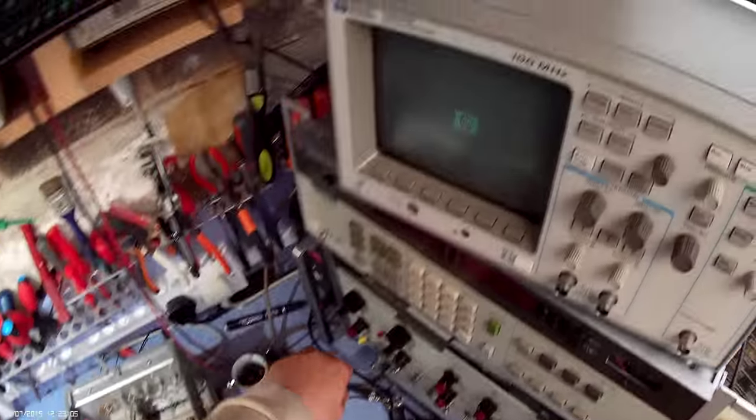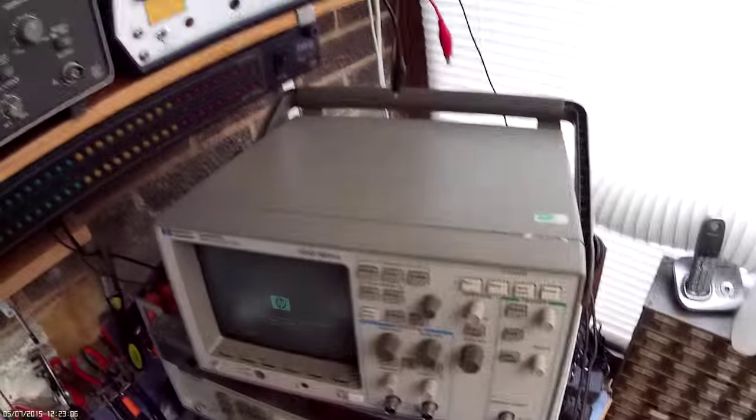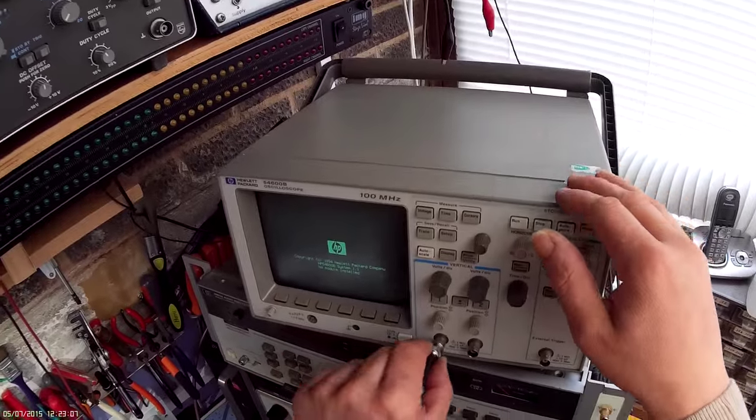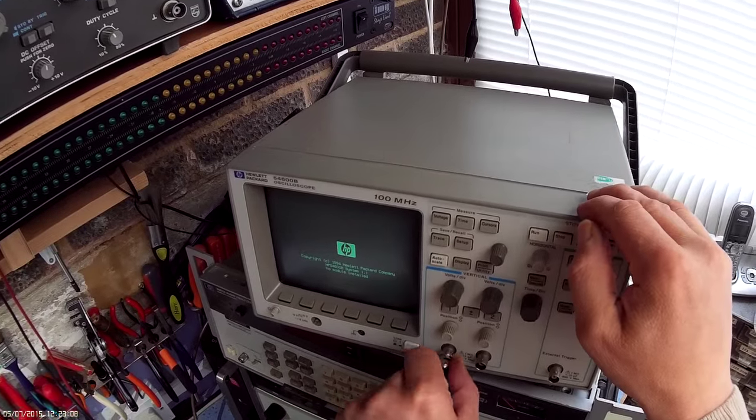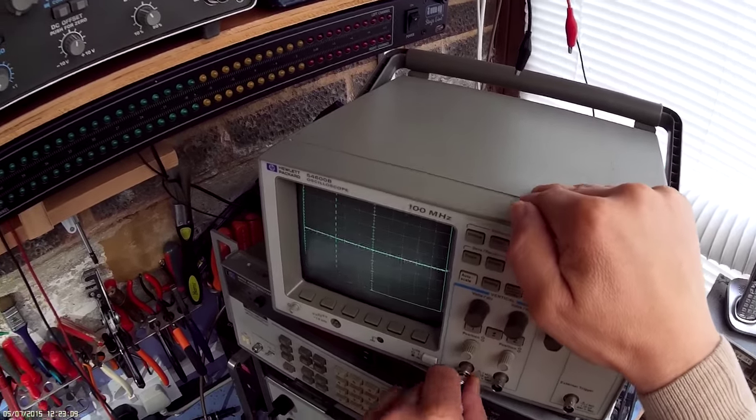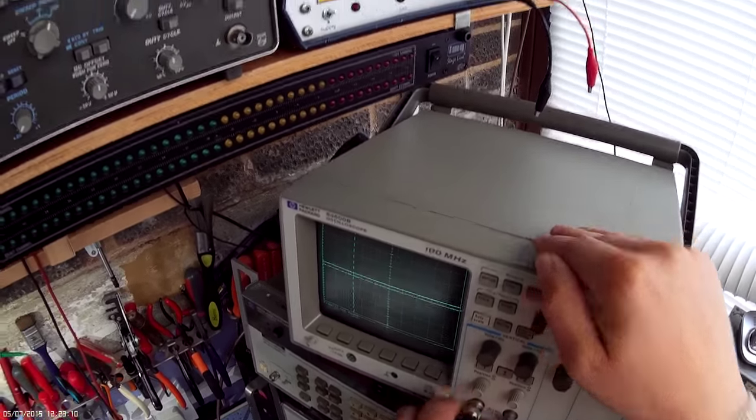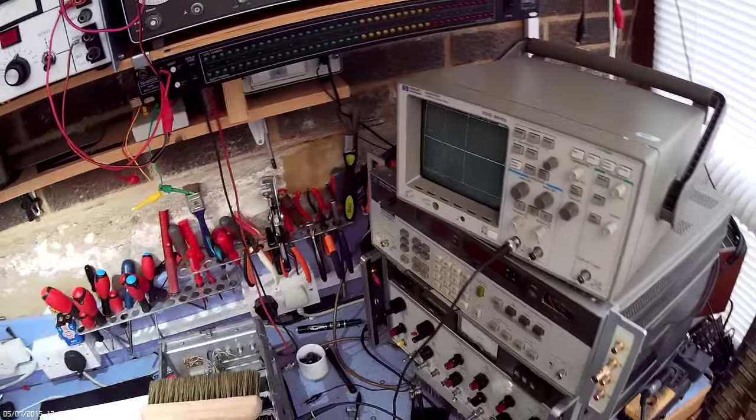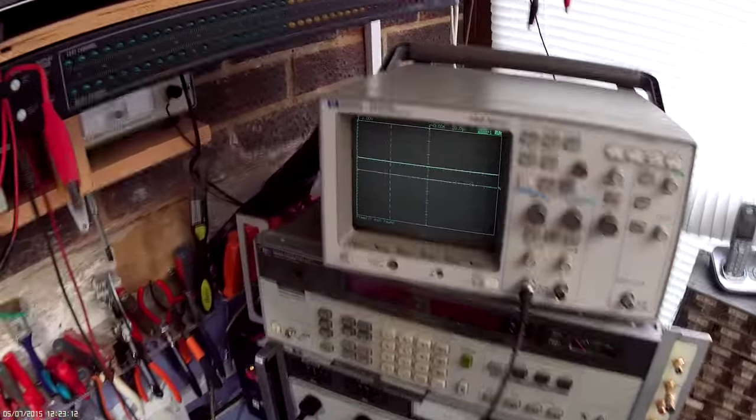Because this is a digital storage scope, it means that when I'm running in a slow trace, you'll be able to see the waveform because it's digitally stored in memory. So that's our initial trace.